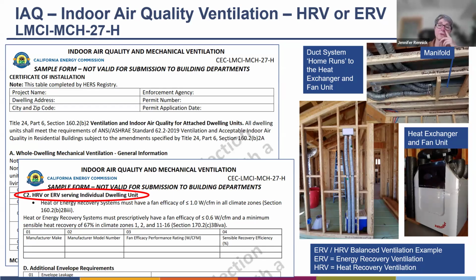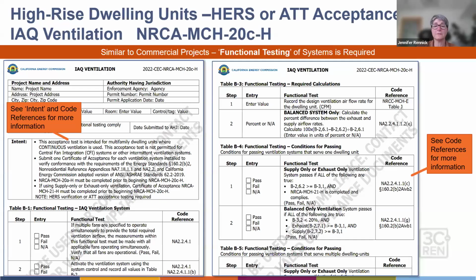And the pictures on the right just show an example of a Zehnder brand. There are a lot of brands out there. This is maybe the most expensive brand, but it was the one chosen for this particular project. Small 3-inch ducts are run throughout the space to provide that fresh air and to exhaust the, quote unquote, stale air through the heat exchanger, thereby allowing the occupants to have tempered fresh air in their space. And it operates continuously.